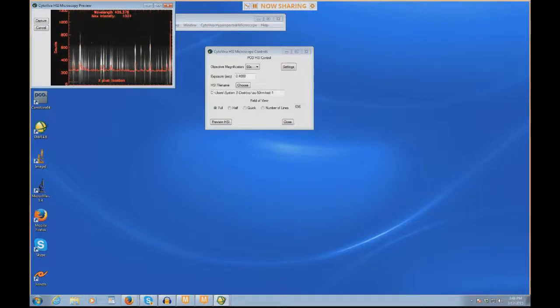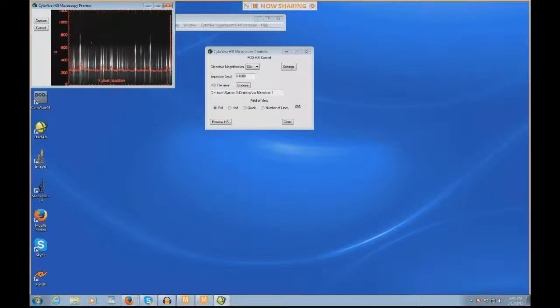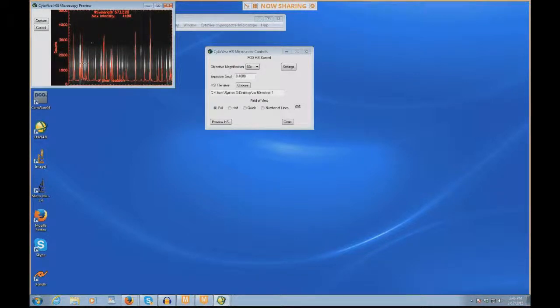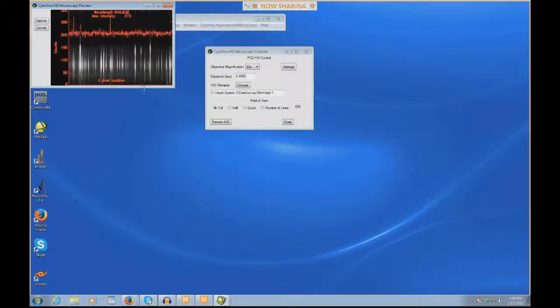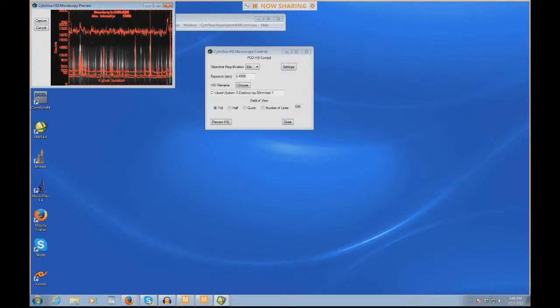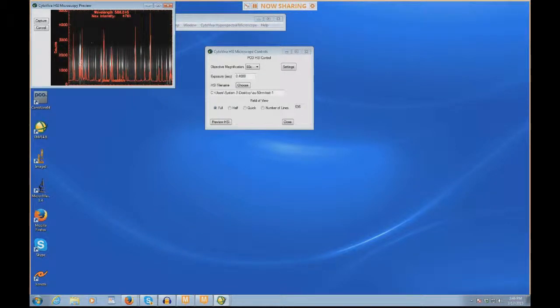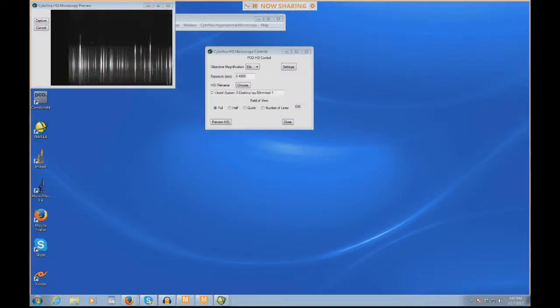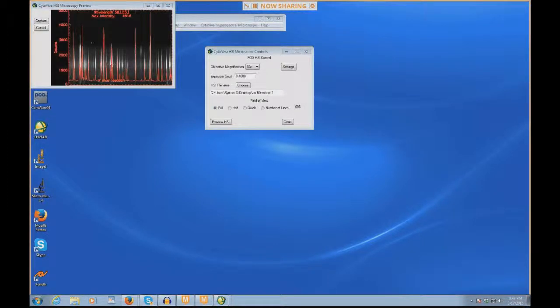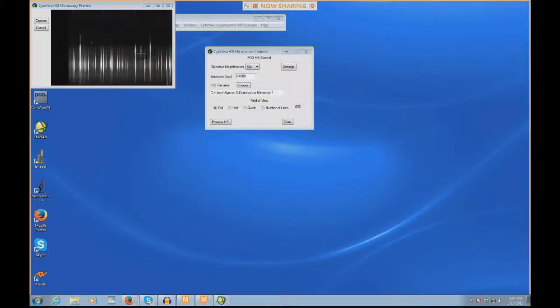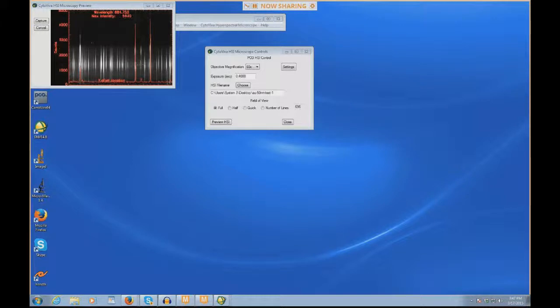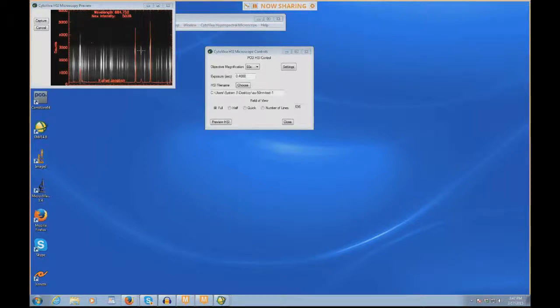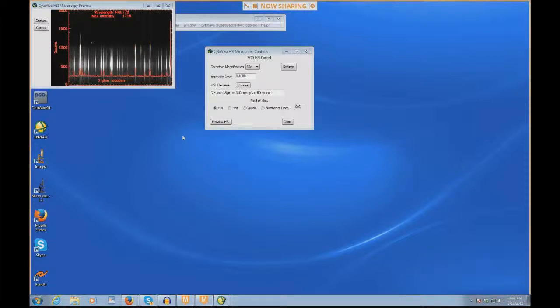On the preview window, X is the X pixel location on the camera. This represents spatial. Y represents not only the intensity counts here as these red peaks, but also spectrum. This wavelength changes as I move the cursor around this window. We can see that most of the data here seems to have a bright area right about 560 nanometers or so. This particle almost seems to have a peak here and then another intensity peak here at about 684. This can kind of give you an idea of spectrally what your material is doing.